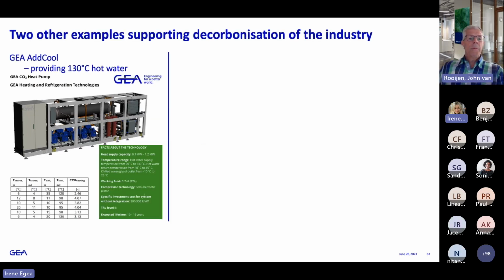One of the other examples, and you see it is also in the format of the Annex 85 sheet, is the GEA AddCool. It is a CO2 heat pump initially developed internally for spray drying processes, where on one side we generate chilled water for the milk preparation part, and with this waste heat we are now generating hot water of 130 degrees, being able to heat up the air for the dryer up to 120 degrees. Temperatures can range from 50 degrees up to 130. One important aspect to mention is that, as CO2 runs supercritical, you should have a large delta T on your heat sink side. This will gradually increase the COP.